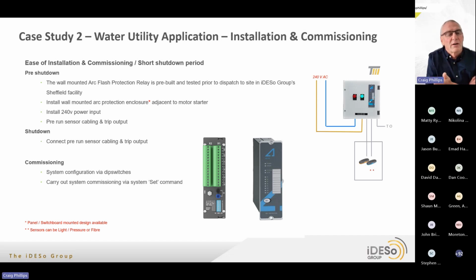Our approach is to very much try and do much of the pre-work prior to any shutdown. So that involves installing the power supply and pre-running any sensor cable and the trip output cabling. And then when we come to shutdown, all we've got to do is connect the pre-run sensor cabling and trip outputs.